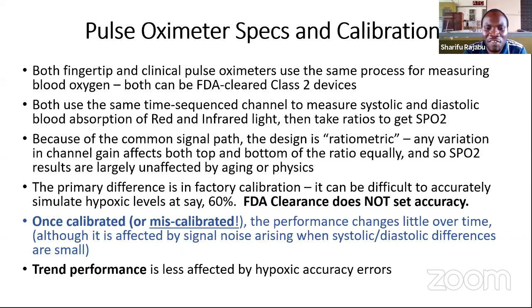Even the cheaper pulse oximeters, known as fingertip pulse oximeters, are already cleared by the FDA, because most of the time they are calibrated using a pulse oximeter simulator or vital sign simulator at normal levels of oxygen saturation, maybe from 90% to 99%. So it is difficult to rely on these pulse oximeters. They are not accurate at oxygen levels below 80%, down to 60%, where they tend to produce inaccurate results. Can you go to the next slide?